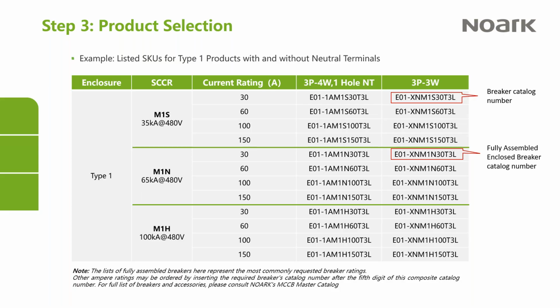So the standard for a molded case breaker drives much different ratings of the product compared to a power circuit breaker. And if you look at where they're used, it's pretty clear why the differences are. A power circuit breaker is typically used in large power systems, above 2,000 amps. Our A series power breakers range in frame sizes from 2,000, 3,200 to 4,000 amps. And that's typically used in switchgear or as the main of a very large switchboard.